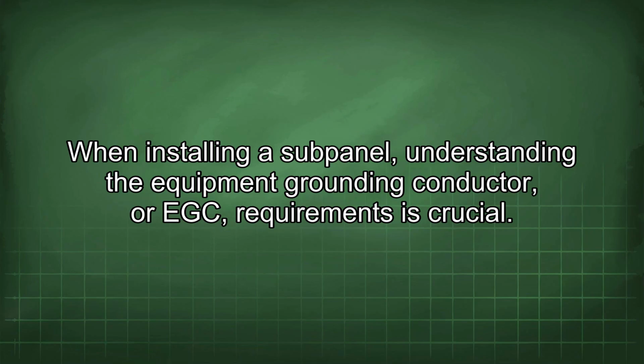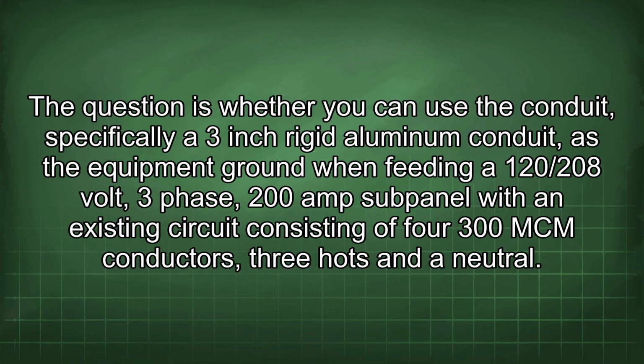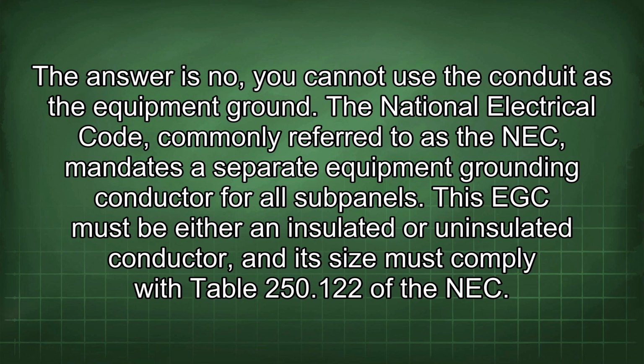When installing a subpanel, understanding the equipment grounding conductor, or EGC, requirements is crucial. The question is whether you can use a conduit, specifically a 3-inch rigid aluminum conduit, as the equipment ground when feeding a 120/208 volt, 3-phase, 200 amp subpanel with an existing circuit consisting of 4 300 mcm conductors, 3 hots and a neutral. The answer is no, you cannot use the conduit as the equipment ground.